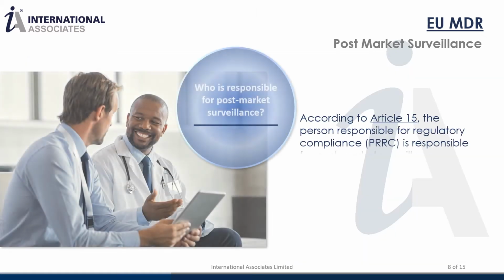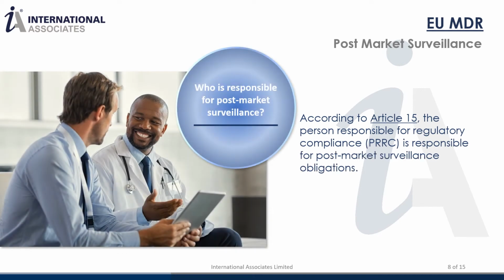According to Article 15 of the Medical Device Regulation, the person responsible for regulatory compliance, the PRRC, is responsible for post-market surveillance obligations. The manufacturer must nominate this person according to the competencies stated in this same article. Also, the ISO TR 20416/2020, Chapter 5.4 relating to responsibilities and authorities, states that top management must define the post-market surveillance team.